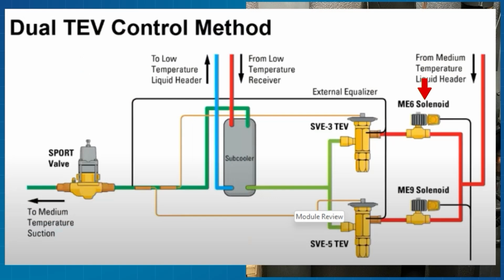When it warms up to 50 degrees, I'm gonna turn this on. Then I'm gonna set up a stage: if this hits 55 degrees, I'm gonna switch, turn this off and turn this guy on. At 60 degrees, if this thing is still climbing in temp, I'm gonna turn them both on. I'll have 3 stages of subcooling. So when I walk into this store, I may walk in at maybe 55 or 60 degrees, that's okay, it's in its range. That's the downside of using this setup, is I gotta have a big enough gap for those to cycle.